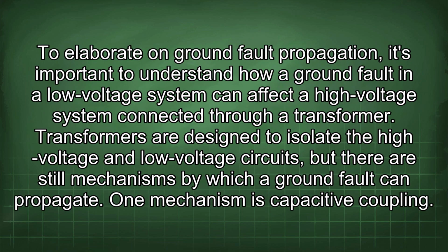To elaborate on ground fault propagation, it's important to understand how a ground fault in a low voltage system can affect a high voltage system connected to a transformer. Transformers are designed to isolate the high voltage and low voltage circuits, but there are still mechanisms by which a ground fault can propagate. One mechanism is capacitive coupling.